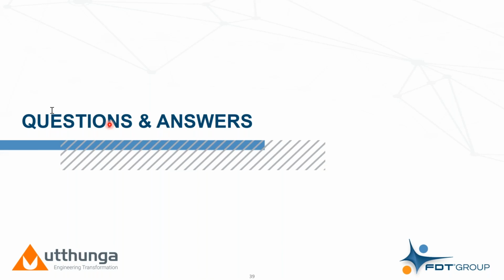So the question was asked, does the FDT 3 server support firmware updates of field devices? And an example is like CAN open. To be very specific about this, the server itself doesn't have to directly do that. It's actually the DTM for the device that would have that responsibility. And the server will support that activity as long as the DTM is capable of doing firmware updates.